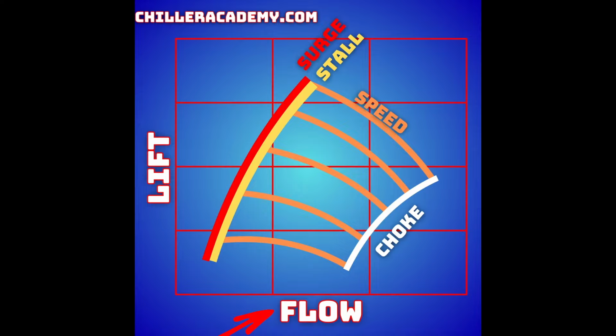So flow could be correlated to your actual inlet guide vane position. This is where, if there's a refrigerant charge issue, or if there's a guide vane issue, things of that nature, all of those things affect your flow through the compressor. So that's what we're having to maintain. So if we have high flow but low lift, guess where we land? In choke. Now, there are scenarios where we could have a low load, so we're derating the compressor and have low lift, but if our flow still gets low enough and our speed is low enough on the machine, we can still push into a surge state even at lower loads.